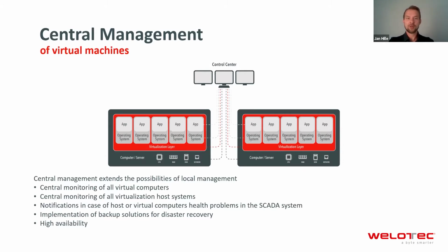We have some central monitoring of all the virtual computers' health state, also some central monitoring of the virtualization host system, meaning we could have the central management solution, for example, in the SCADA system. We just need some kind of network connection to the management of the host system, and we can notify the operator in case anything happens in this virtual system.